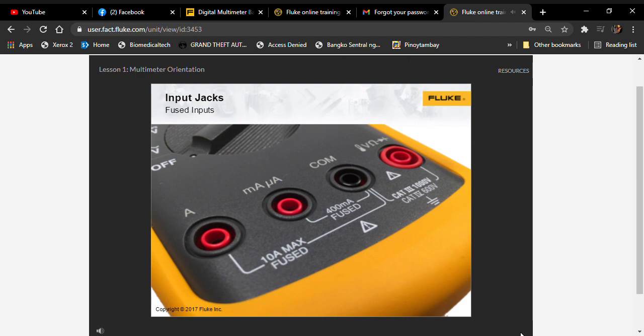When measuring current, it flows through the multimeter with little resistance. Flow from an overcurrent condition could damage the multimeter or injure you. So in Fluke meters, the current inputs are fused in order to quickly open such a circuit condition. The maximum allowable current ratings are marked near the inputs. It's important that you observe the markings near the input jacks. Some meters do not have fuses protecting these inputs.